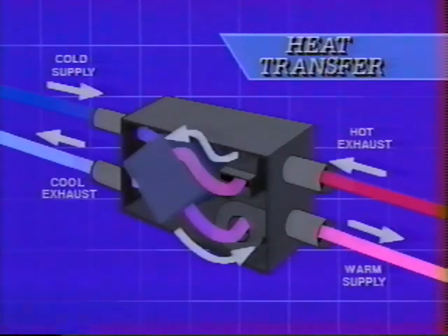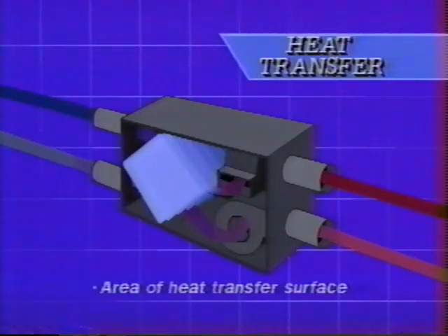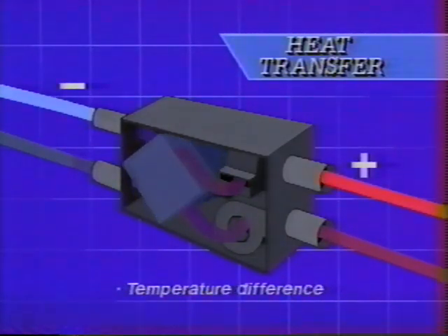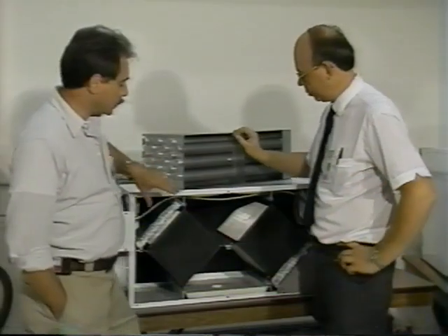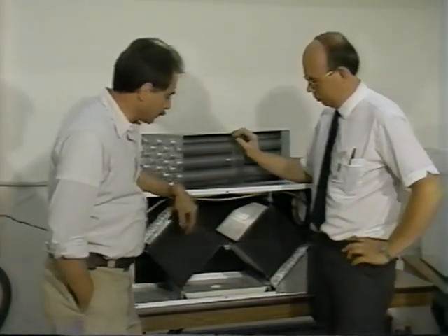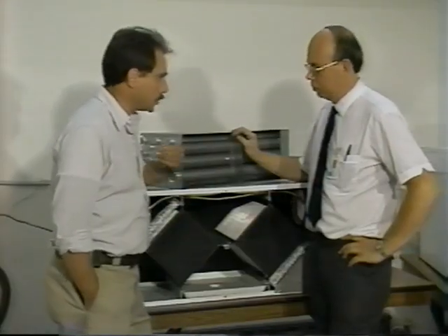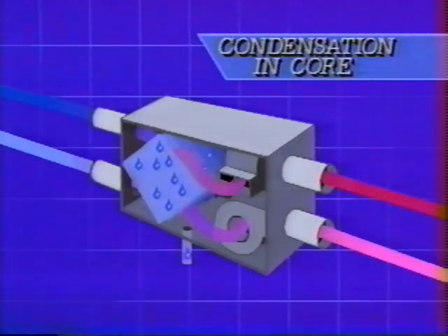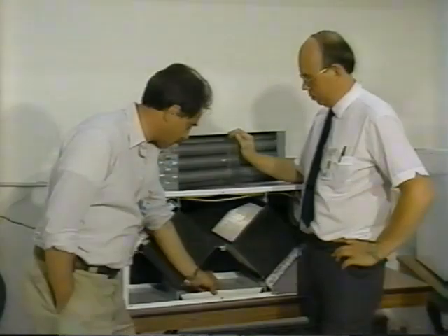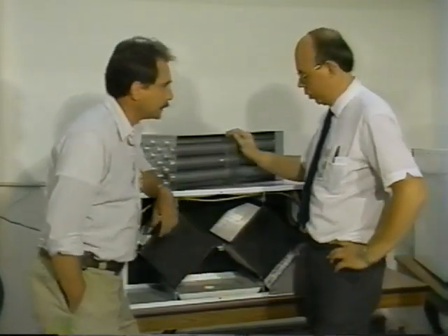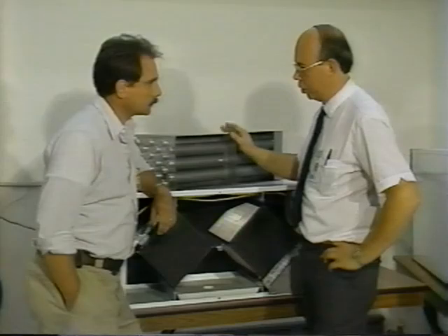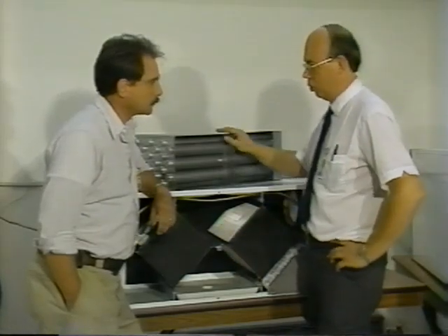A couple of the important aspects of heat transfer in the cores is the surface area of the core. The greater the surface area, the better the heat transfer, and the temperature difference in the core. The higher the temperature difference, the greater the heat transfer. And presumably one of the problems that can occur here is the fact that as the outgoing humid air from the building is chilled, one can get a condensate, and that condensate is dropped into this drain, this plate, and then drained away. It's very important that the installer make sure that this drain is connected up for the units.